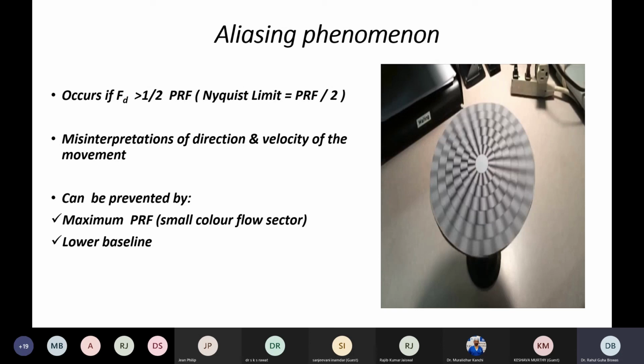So what is the Nyquist limit? The Nyquist limit is that if a particular velocity of an object is more than the pulse repetition frequency, then there is something called aliasing which happens. So the frequency at which the piezoelectric crystal is sending out the sound wave, if the object of interrogation has a much higher velocity, we will have something called aliasing. What is aliasing? Aliasing is basically the complete misrepresentation of the velocity data and the direction of movement.